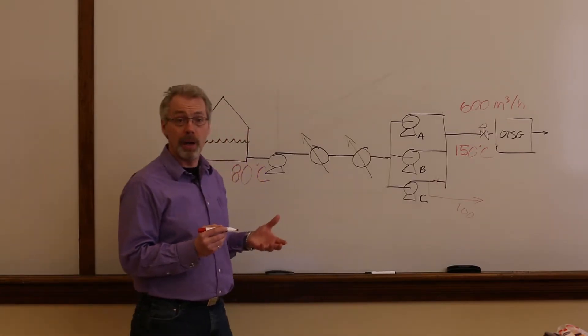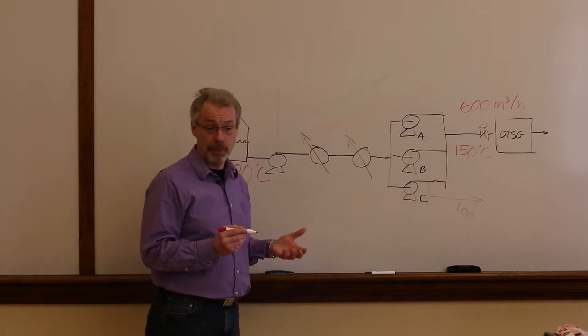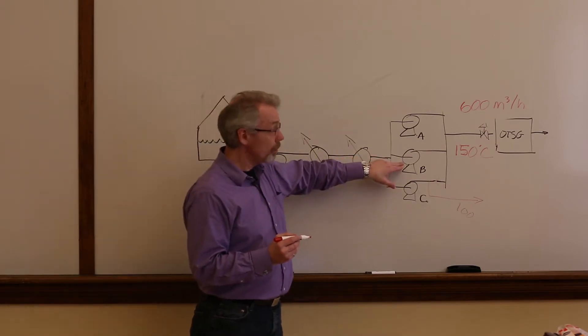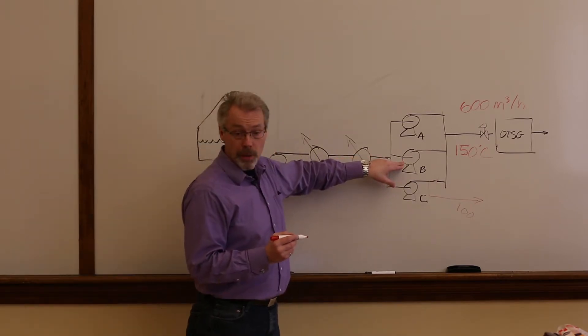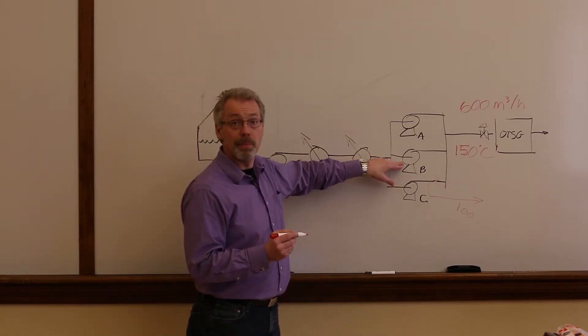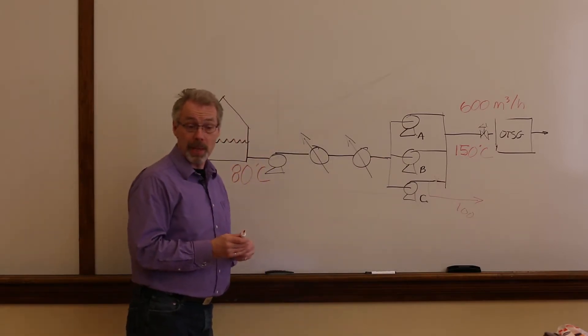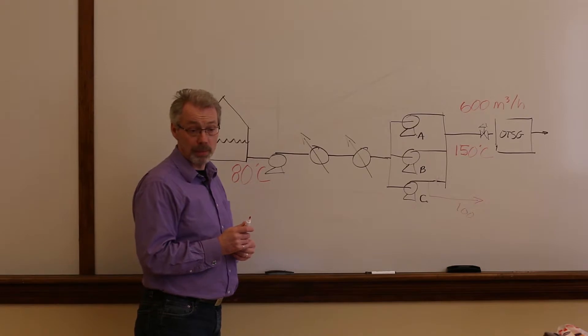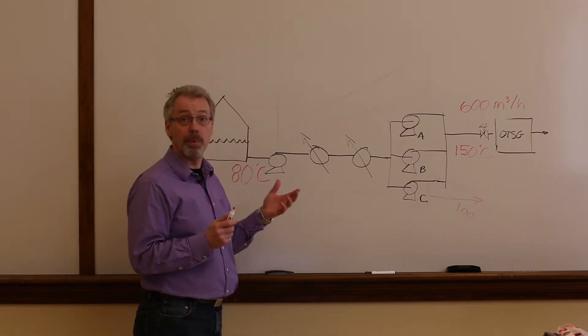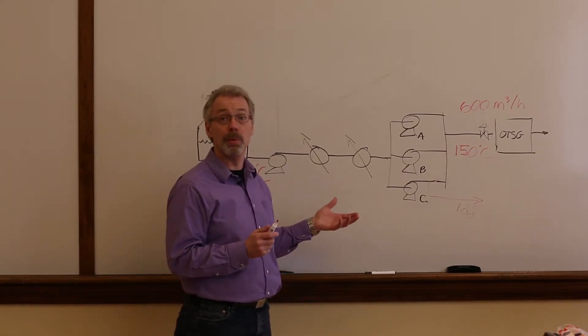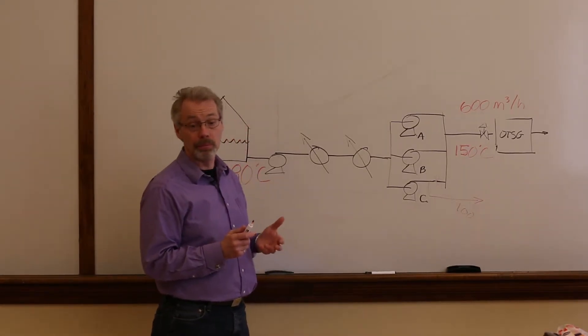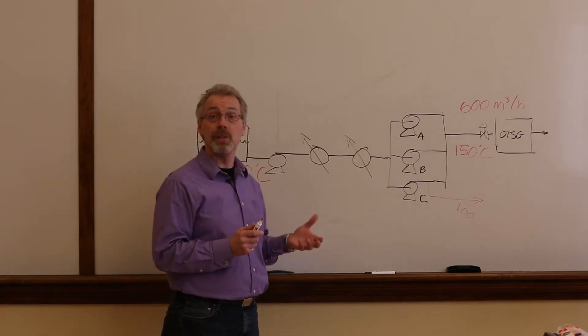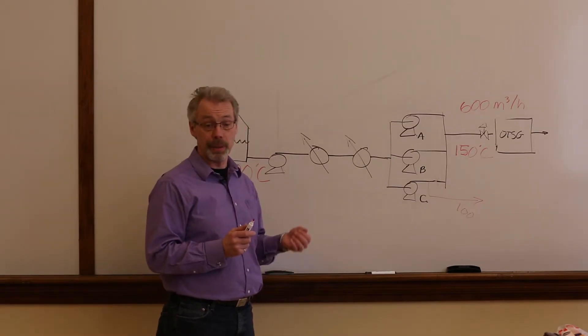Shutting down a pump is similar. Pump B is slowly blocked in and operated at minimum flow. Pumps A and C deliver 600 cubic metres an hour to the OTSG, and pump B wastes 100 cubic metres an hour. The boiler feed water sees a 60 degree rise.